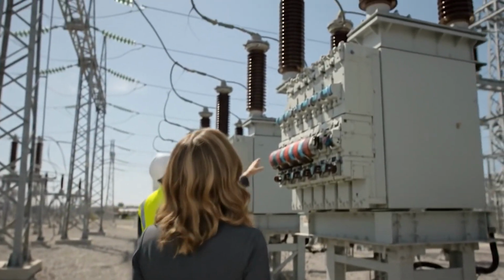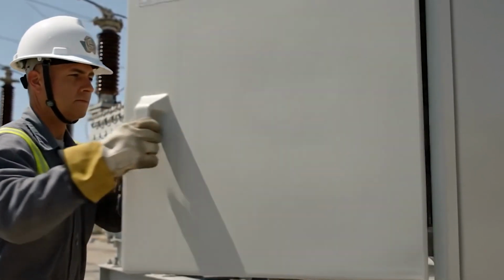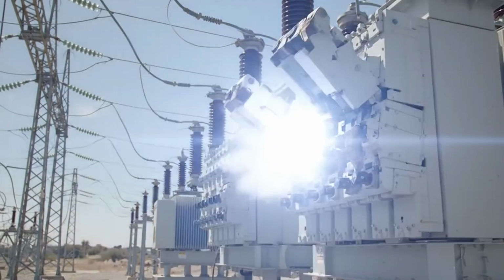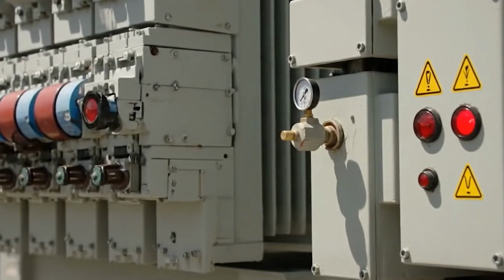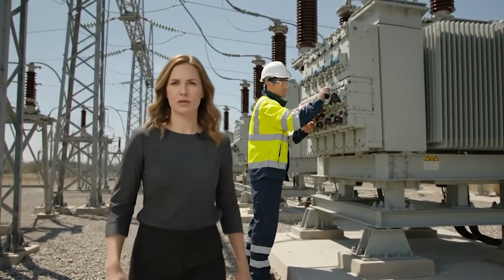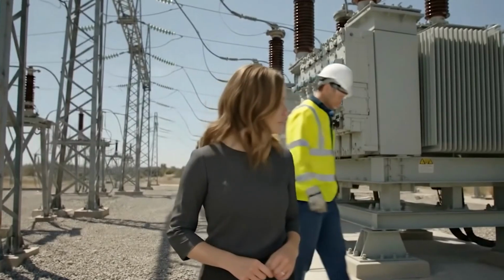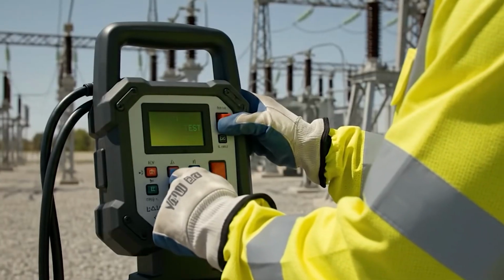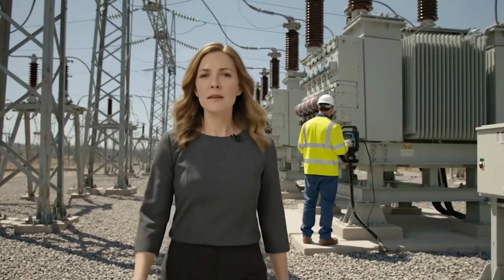A technician walks me through the breaker yard. These aren't light switches. They're machines filled with insulating gas, designed to interrupt currents of 50,000 amps or more. When they trip, the energy released is like a small explosion. Contained, controlled, but violent. He tells me they test these regularly, because when you need them, there's no second chance.